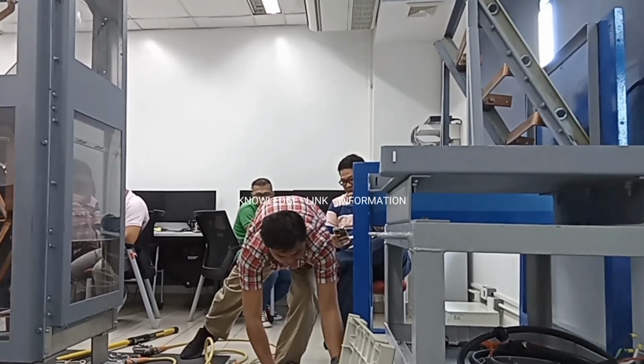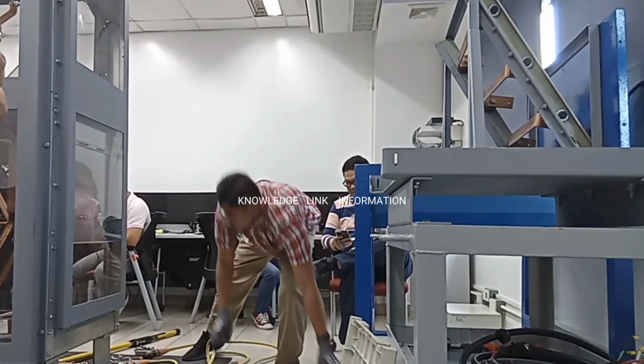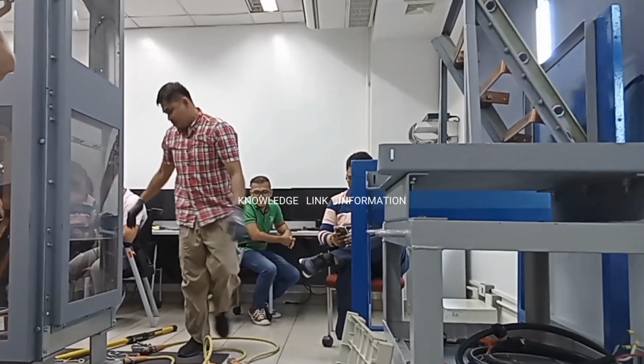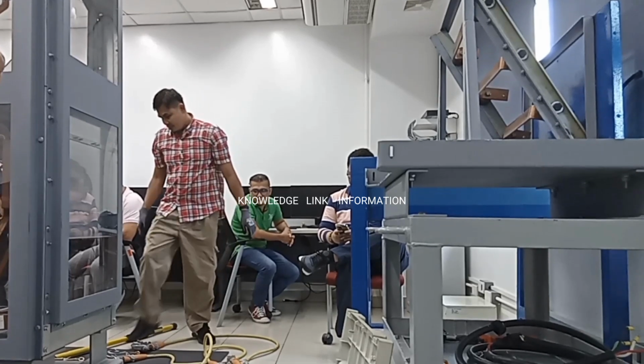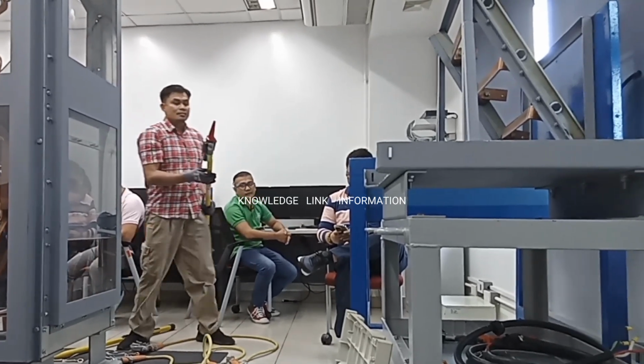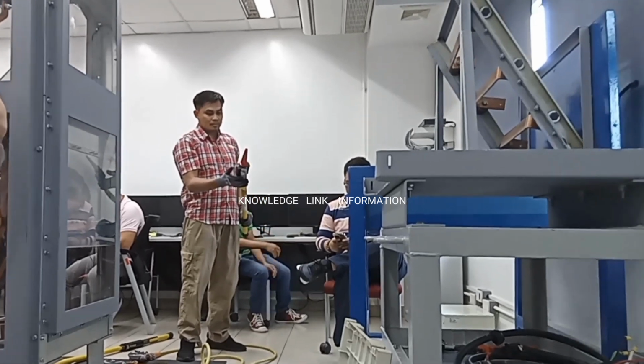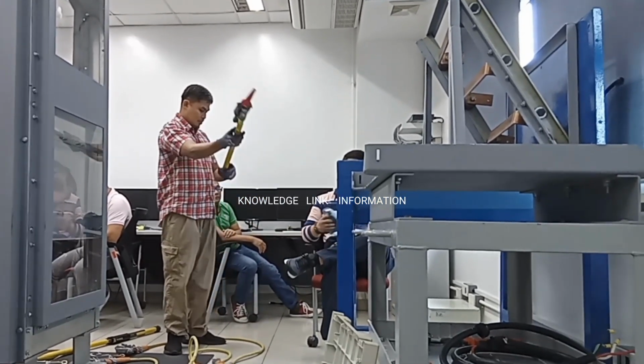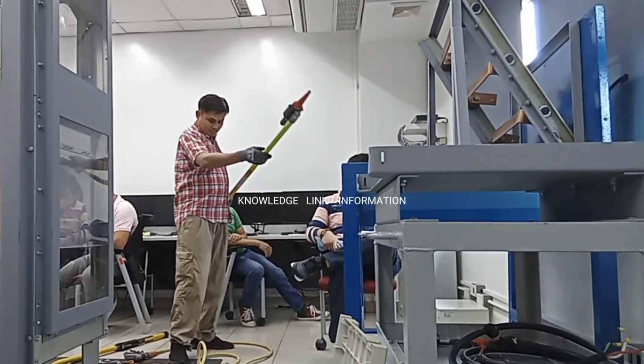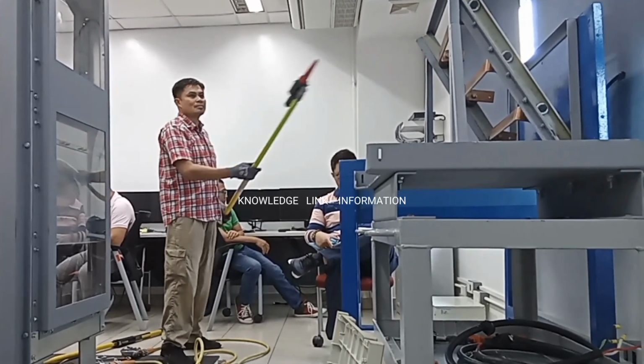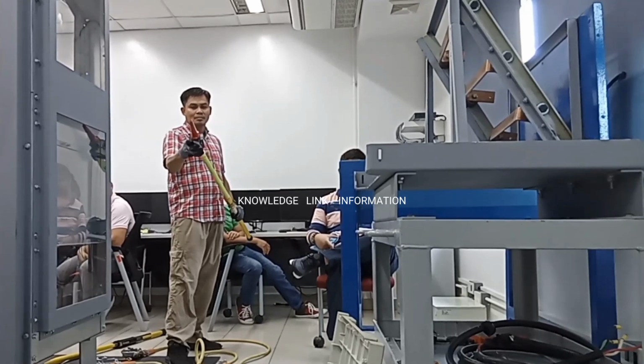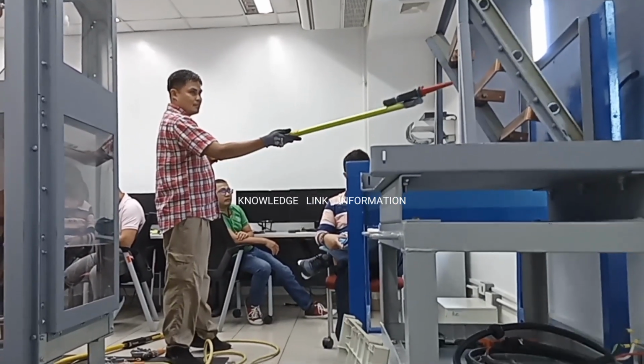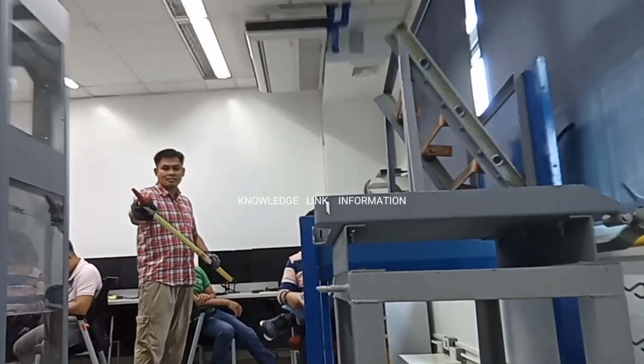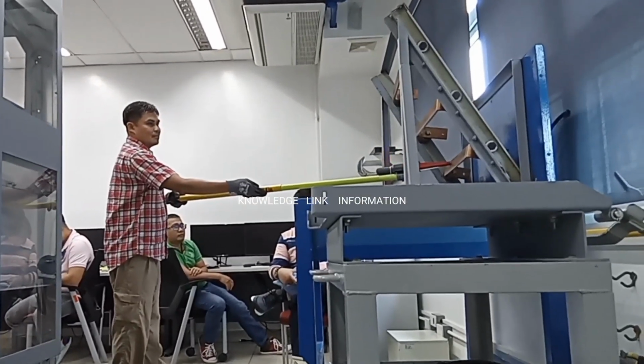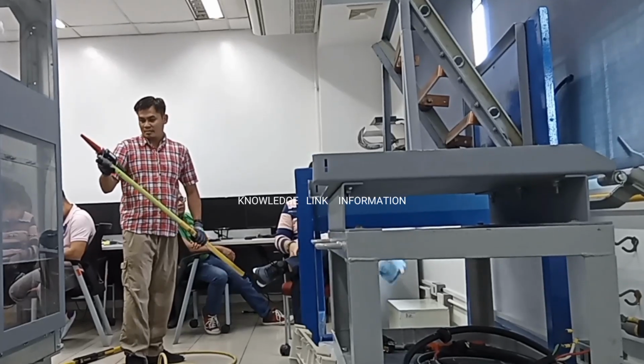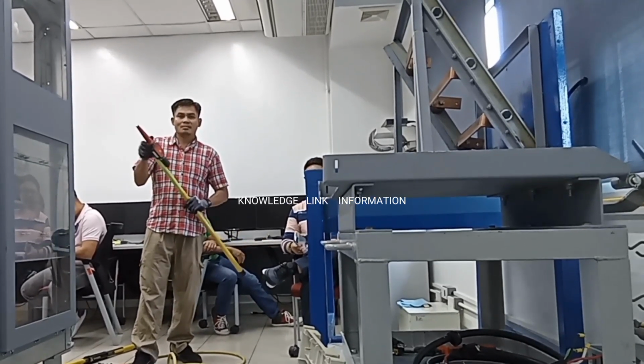Number 11. Arrange and inspect the cable leads and clamps of the earthing connector. Never use the earthing connector if any defects are found. Number 12. Prove that the bus bar is dead, or without any voltage, by using a non-contact voltage tester. Extend the telescopic stick, and select the voltage range according to the bus bar voltage. Always confirm the normal operation of the voltage tester before and after a test operation on every bus bar. We can start the bus bar earthing connection if we prove that there is no voltage present on the bus bar.